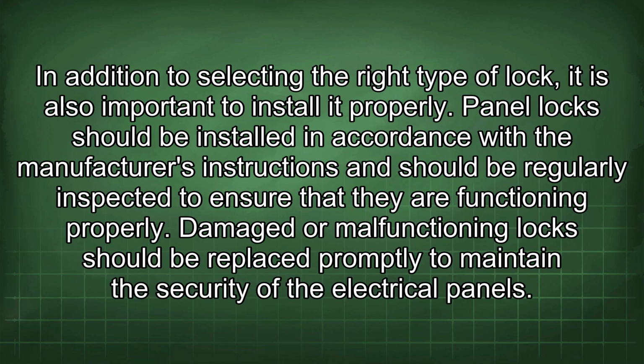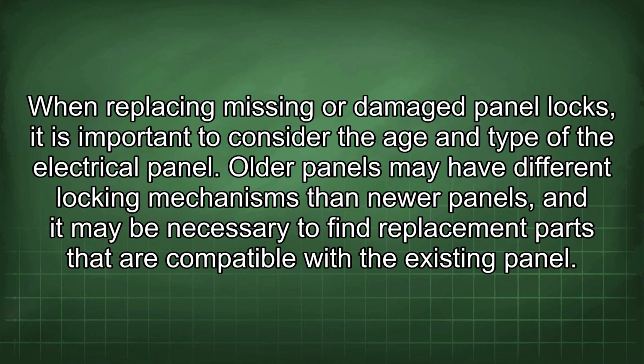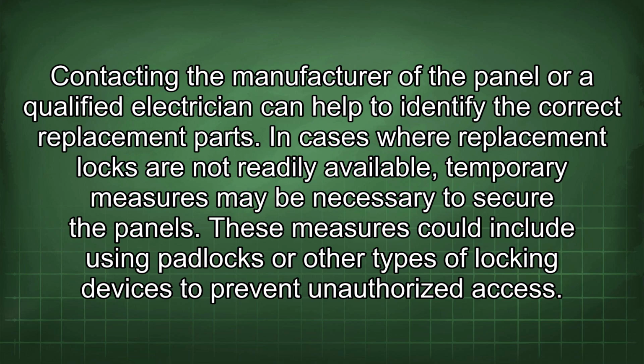In addition to selecting the right type of lock, it is also important to install it properly. Panel locks should be installed in accordance with the manufacturer's instructions and should be regularly inspected to ensure that they are functioning properly. Damaged or malfunctioning locks should be replaced promptly to maintain the security of the electrical panels. When replacing missing or damaged panel locks, it is important to consider the age and type of the electrical panel. Older panels may have different locking mechanisms than newer panels, and it may be necessary to find replacement parts that are compatible with the existing panel. Contacting the manufacturer of the panel or a qualified electrician can help to identify the correct replacement parts.